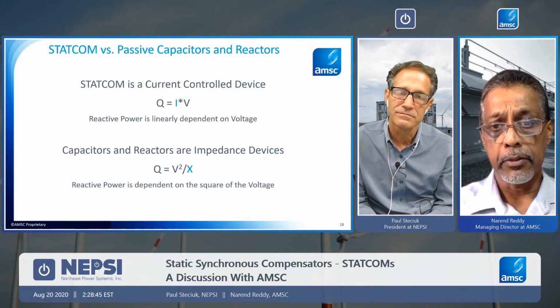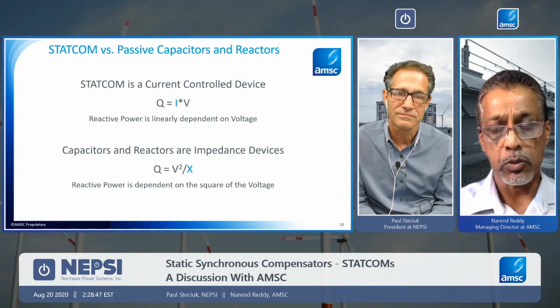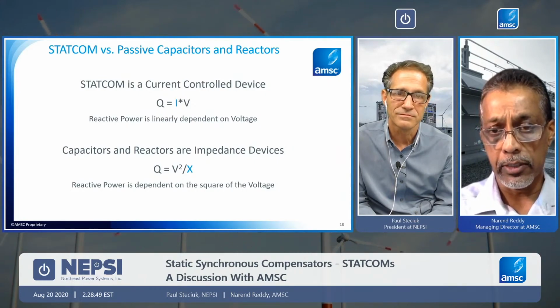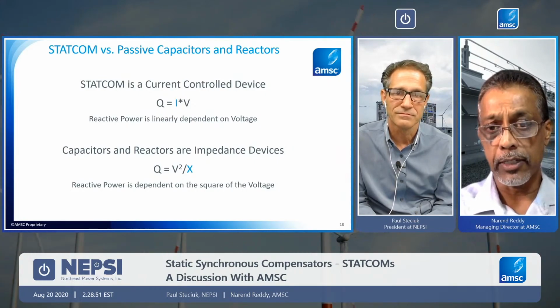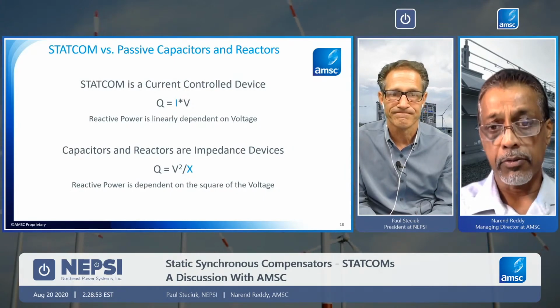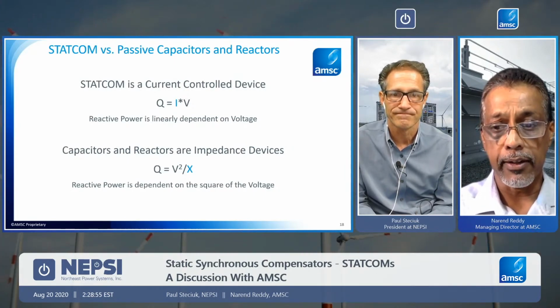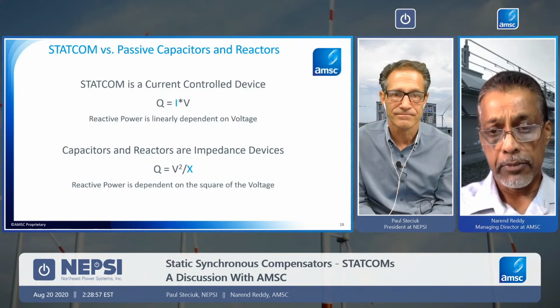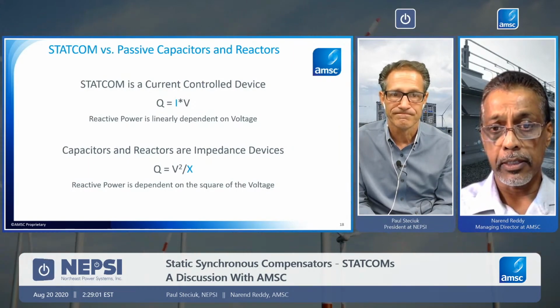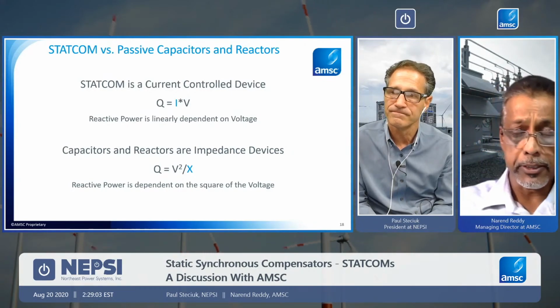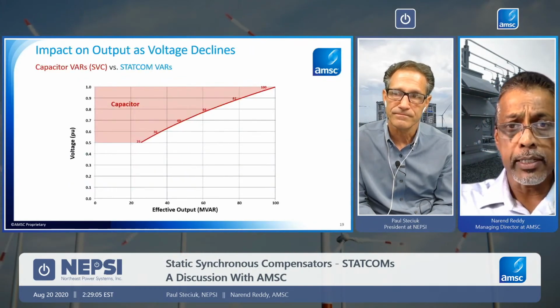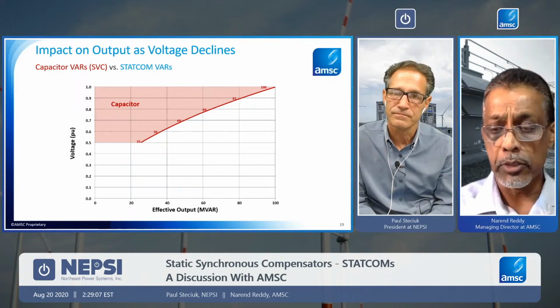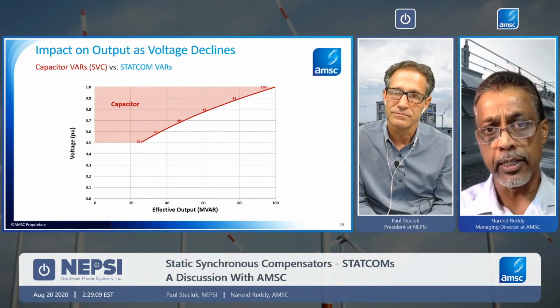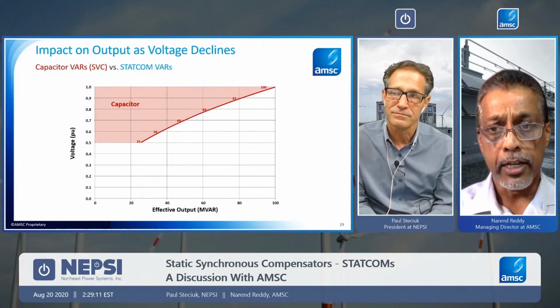They are what we call impedance devices. So you really have a certain voltage that you're imposing onto these devices. And like you said, very correctly, the net output of these devices, the Q, is dependent on the square of the voltage. So what does that mean in terms of effectiveness? That's how we look at it, the effectiveness of the vars.